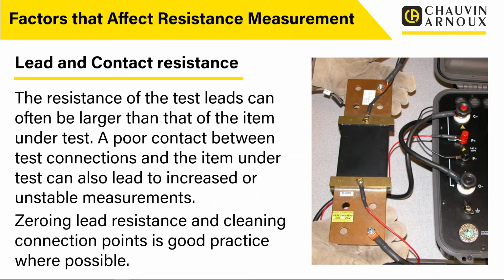Lead and contact resistance. So the resistance of test leads can often be larger than that of the item under test. And in many cases it is: you've got a very low resistance you're trying to measure and you've got quite high resistance test leads. A poor contact between test connections and the item under test can also lead to increased or unstable measurement. So it's really important that you've got a good, reliable connection.